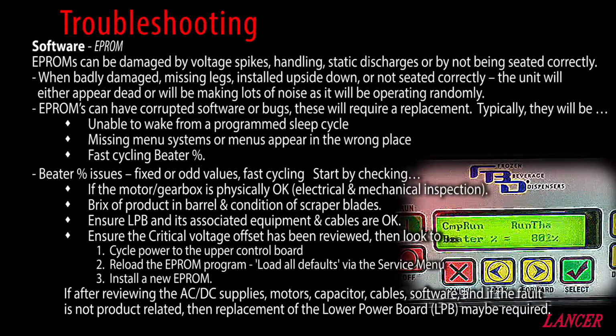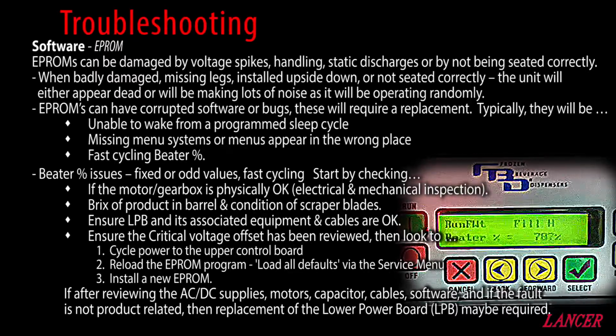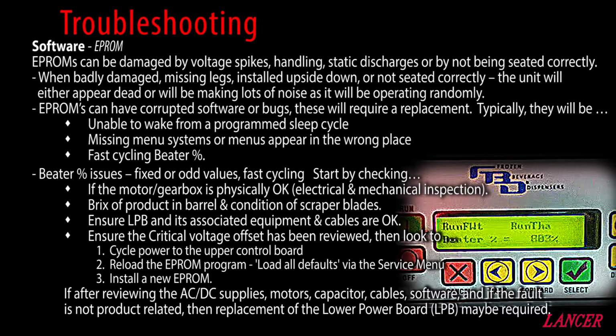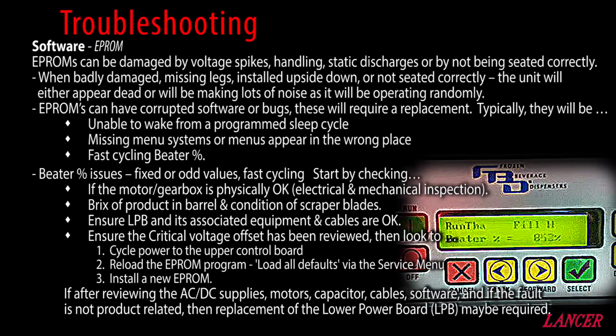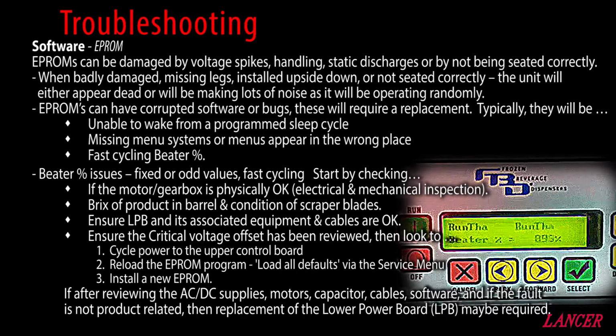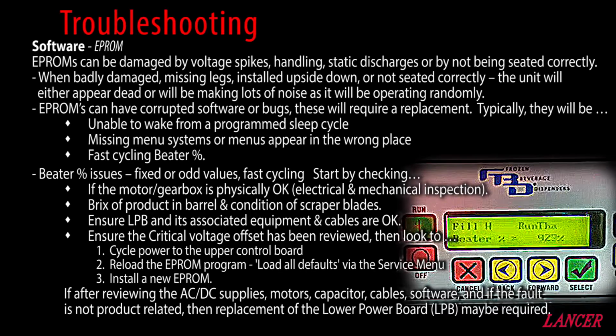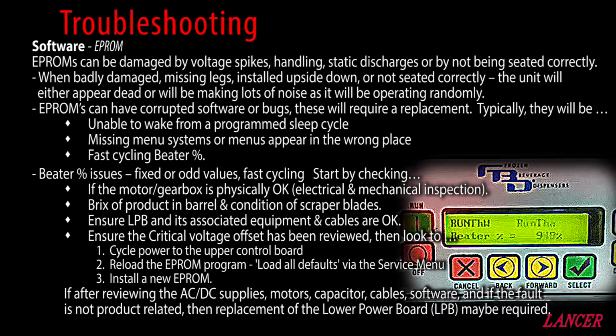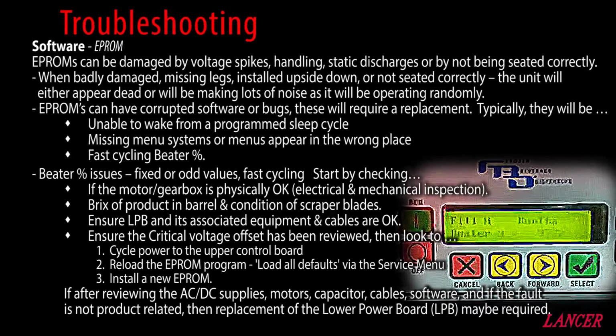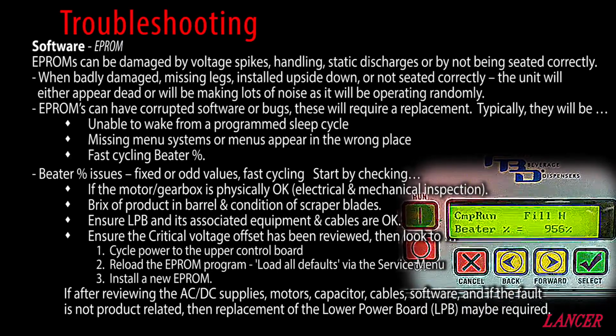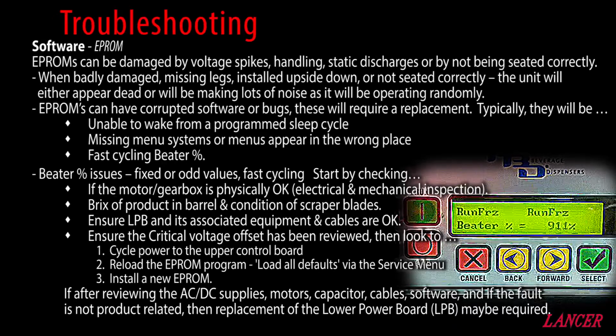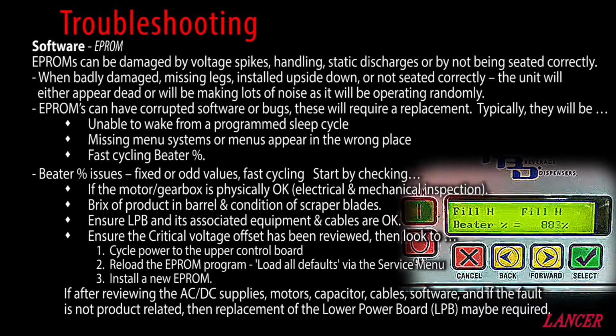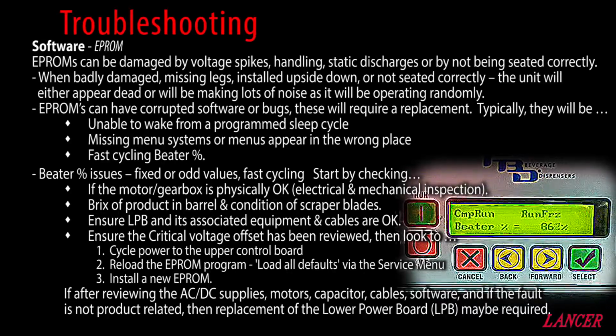When badly damaged, missing legs, or installed upside down or not seated correctly, the unit will either appear dead or be making lots of noise, as it will be operating randomly. EEPROMs can have corrupted software or bugs. These will require a replacement. Typically they will be unable to wake from a program sleep cycle, missing menu systems or menus will appear in the wrong place, or fast cycling beater percentages.